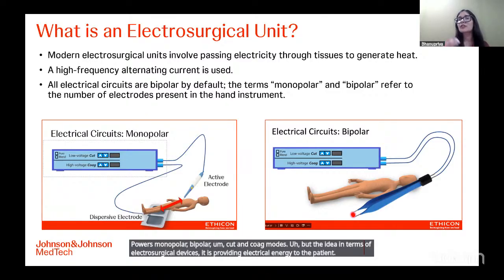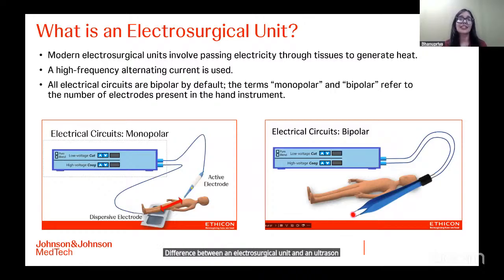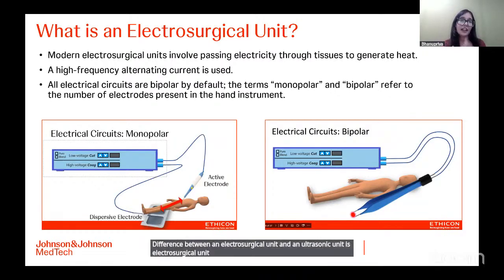The difference between an electrosurgical unit and an ultrasonic unit is that an electrosurgical unit has current. That current passes through the electrodes, through the pencil or the bipolar, into the patient's body. Now you see that a patient has current flowing inside the body. So why does the patient not feel a shock, or get a burn in the body? That is because the circuit is completed and you have a sticky pad which is sucking away all the current which you have transferred into the body back to the generator.